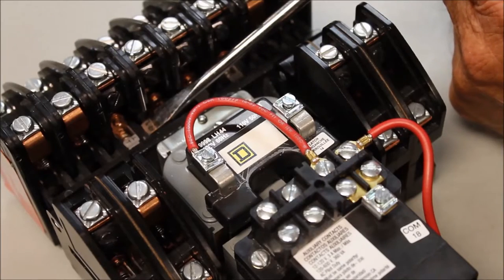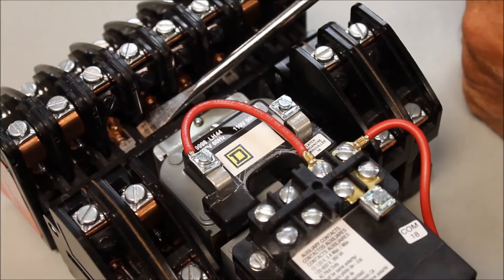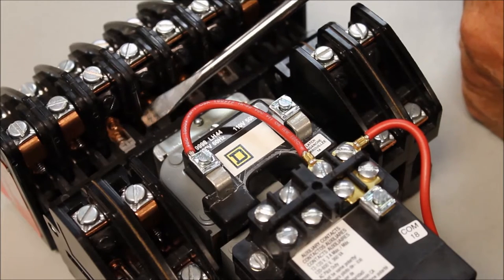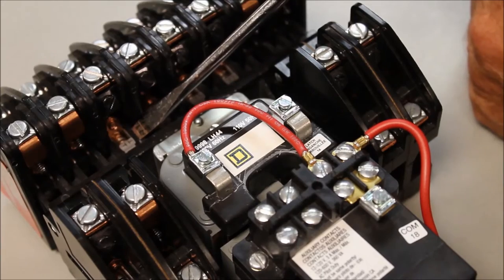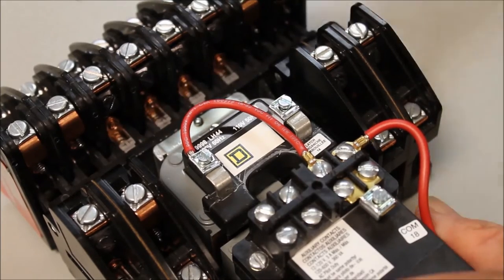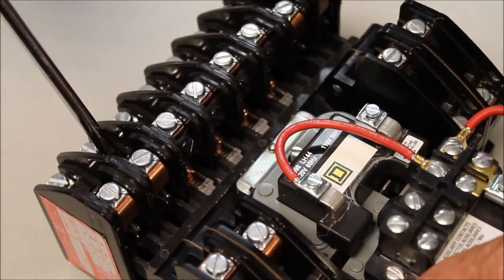The 8903L lighting contactor has contacts that are convertible from normally open to normally closed. On a contactor, you can look at the base of the contact itself for a symbol indicating normally open, or at the top of the contactor there would be a symbol indicating normally closed.